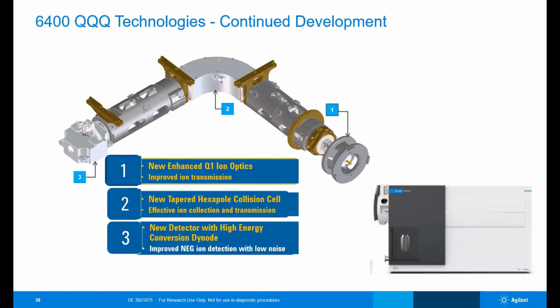Here we can try to understand how 6470 versus Ultivo looks like. 6470 LC triple quad with AJS and APCI source is known for its legendary ruggedness, robustness, and research capabilities. It adds enhanced tuning features for research applications. It is a standard benchtop model, and if you need to do very low or very high masses, you need to go for 6470 LC triple quad. It has the advanced tuning parameter interface. It is an intermediate between the core and the ultra high end model, and it also has the vacuum shield with it, where you don't need to vent the system for cleaning the ion injector.